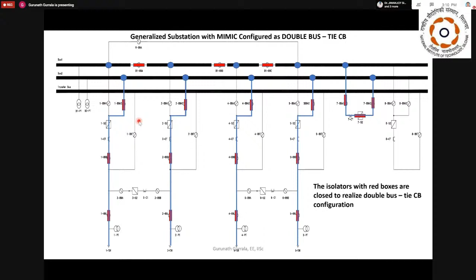Now, how do you implement this? This is something very important. You need to create that scheme inside your bus control unit, and that is practical knowledge you will gain from this kind of work. There is another configuration that you can do, called single bus with transfer. Single bus is one and transfer bus is the bottom. You can see that only the corresponding breaker which connects between bus 1 and the transfer bus is enabled now. Anything else you want to turn on will not turn on. And one important thing you need to take care of is that you can transfer only one feeder at a time to the transfer bus. So you can only transfer like this, one feeder to the other.